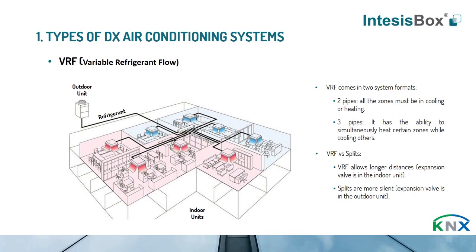In order to make you understand the main differences between the VRF and the multi-split units, the VRF system allows longer distances. Why? Because the expansion valve is located in the indoor unit, and that's why the refrigerant can travel at high pressure.